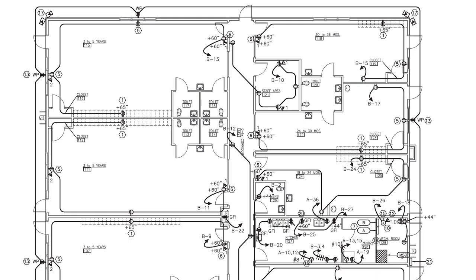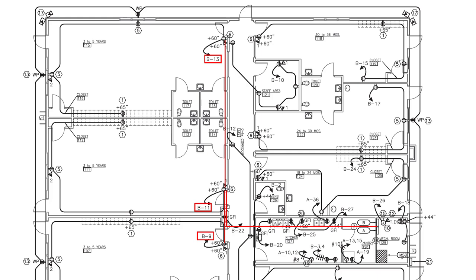With that in mind we're going to group circuits B9, 11, and 13. We're going to start off by running a home run from panel B to the first receptacle for circuit 11. From there we will run a conduit to feed circuit 9 and 13. Then we will run the conduits out to each receptacle. In order to be competitive you have to take every advantage to reduce material and labor costs. Combining multiple circuits into a single home run is one method of doing that. That's called value engineering.